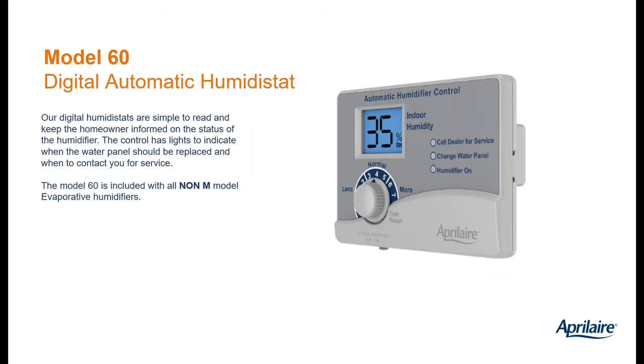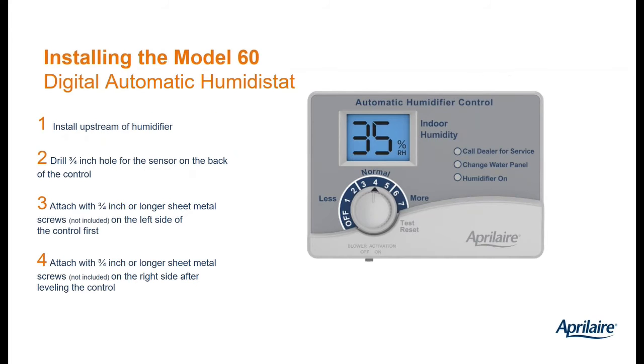If in a given application you want the automatic humidistat, let's say for the digital display, you want it for the indicators, change water panel, call dealer for service, there's an error code, and then you want the feature of the blower activation, which we'll talk about later, but you don't want to run the outside temperature sensor for whatever reason. Either you can't, or aesthetically, the occupant doesn't want you to. You can run the automatic humidistat in manual mode.